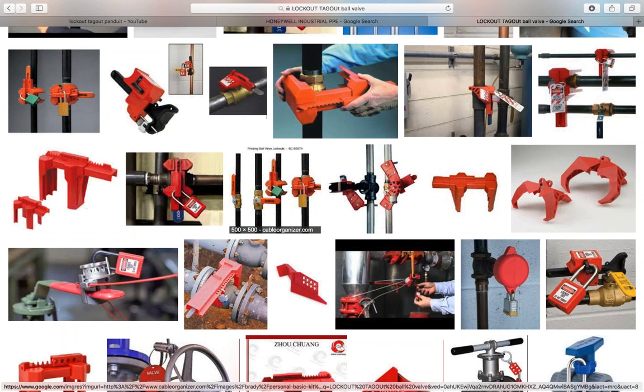If a device, valve, switch, or piece of equipment is locked out, make sure it's properly tagged out as well. Like I said, it's not mandatory, but it is a best practice to do both, okay? We definitely want to do both, but they're not required to do both. OSHA says we can either lock and/or tag.